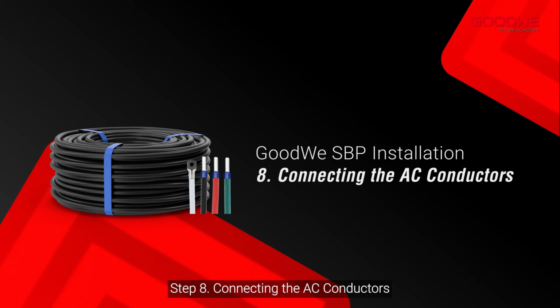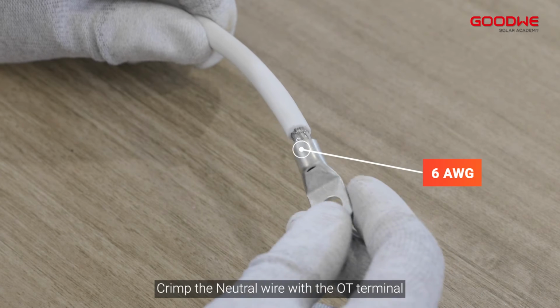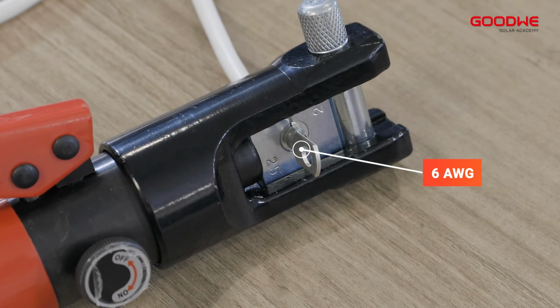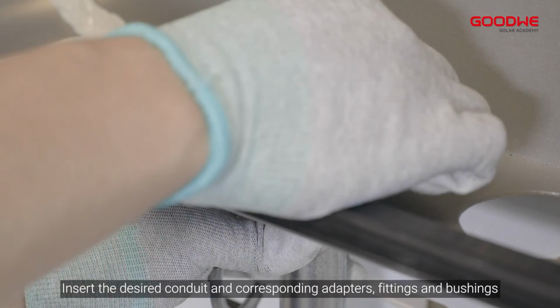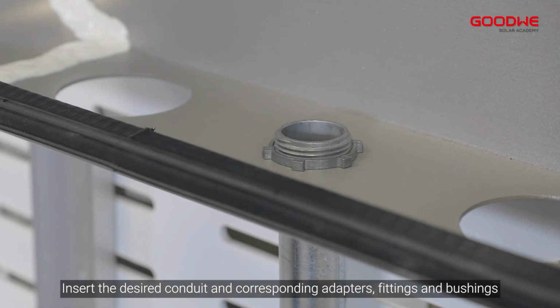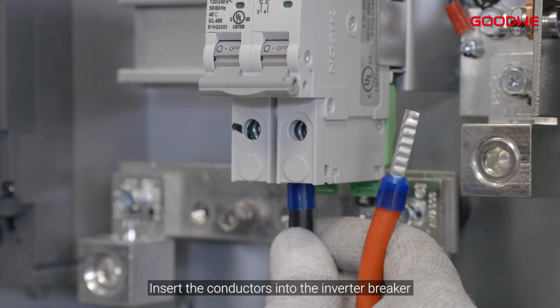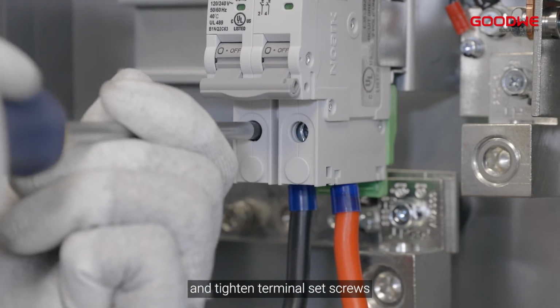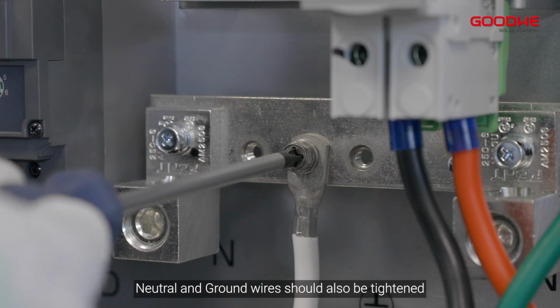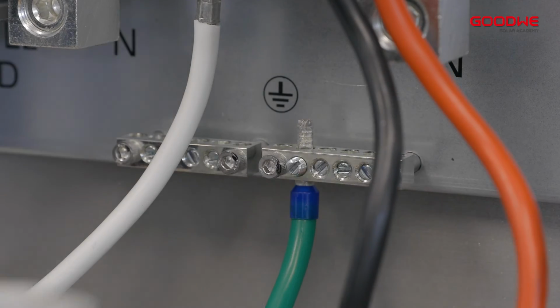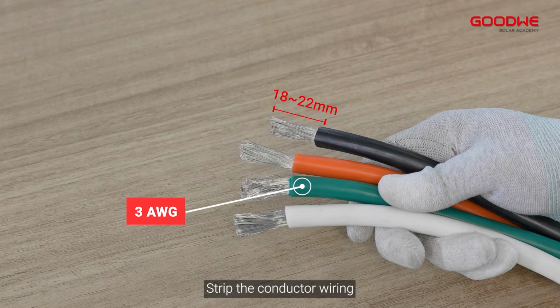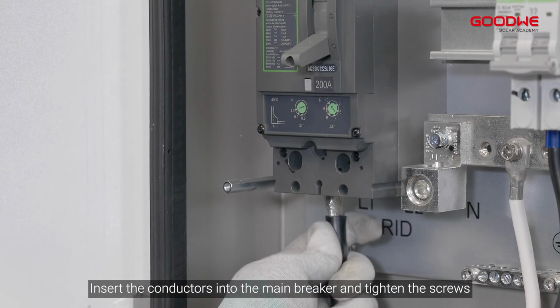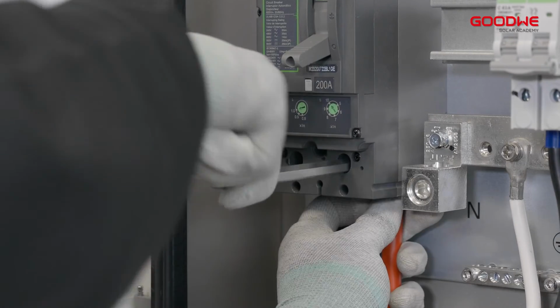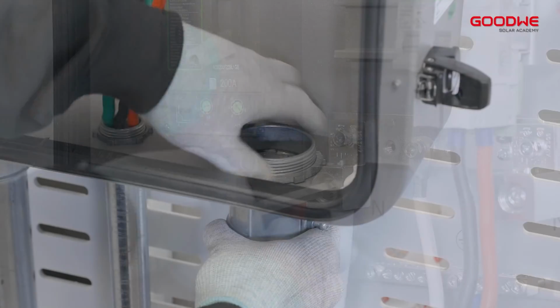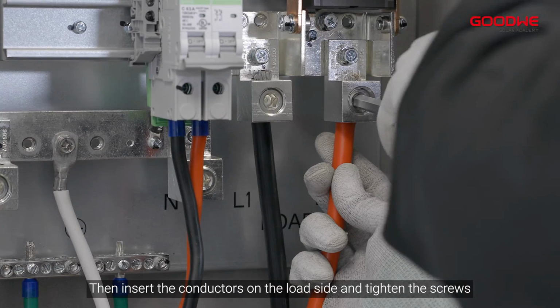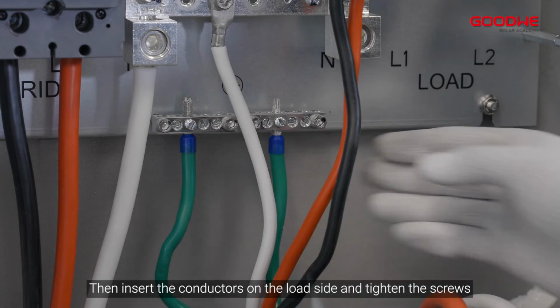Step 8. Connecting the AC conductors. Crimp the neutral wire with the OT terminal. Insert the desired conduit and corresponding adapters, fittings, and bushings. Insert the conductors into the inverter breaker, and tighten terminal set screws. Neutral and ground wires should also be tightened. Strip the conductor wiring. Insert the conductors into the main breaker and tighten the screws. Using the same procedure, insert the conductors on the load side and tighten the screws.